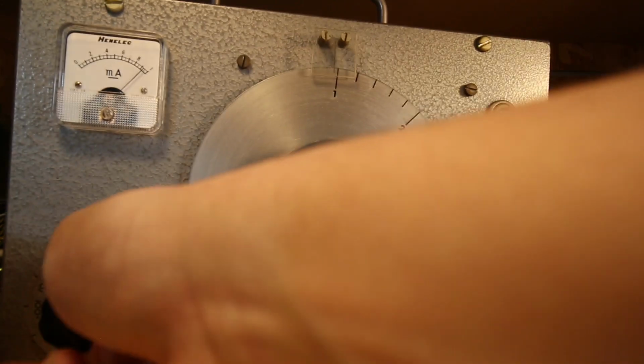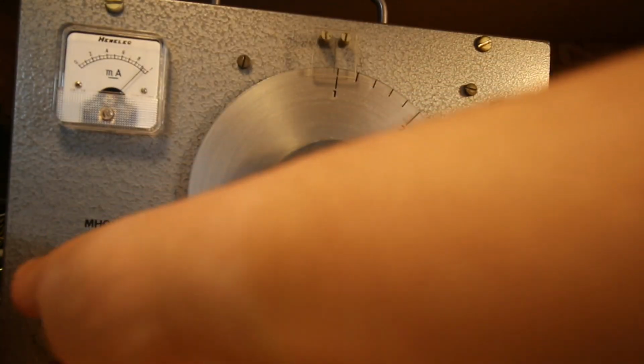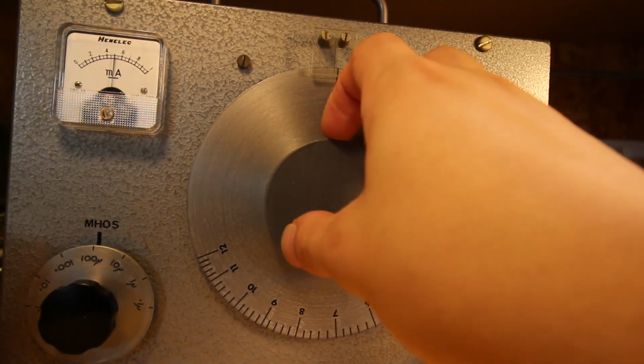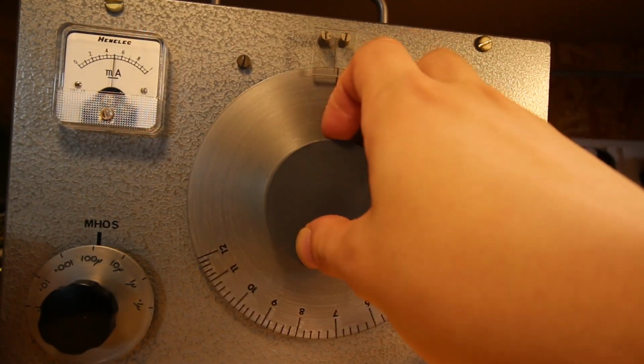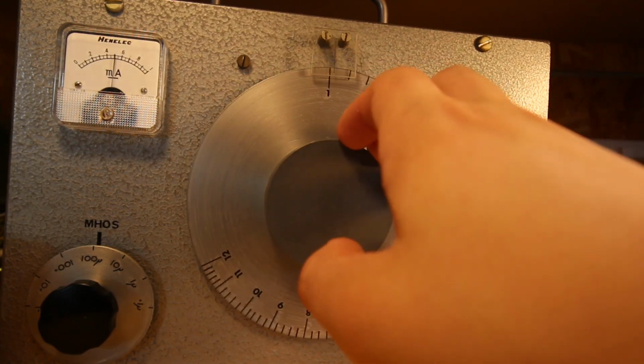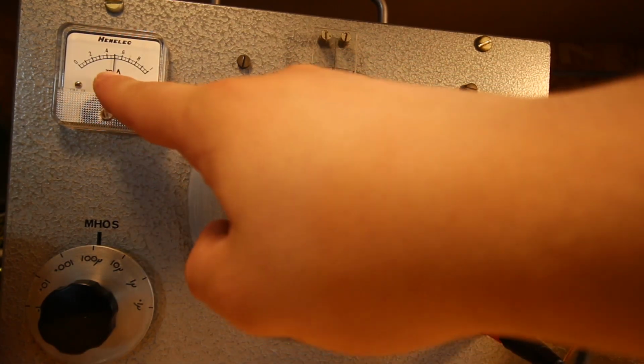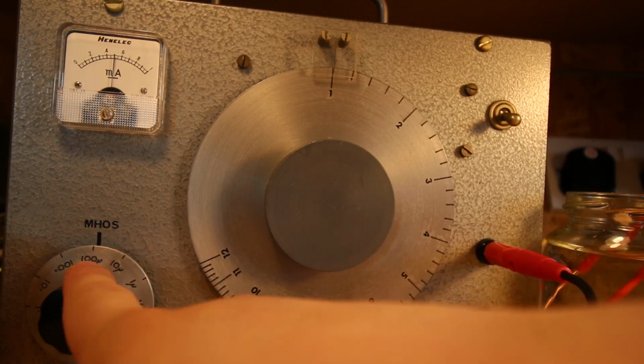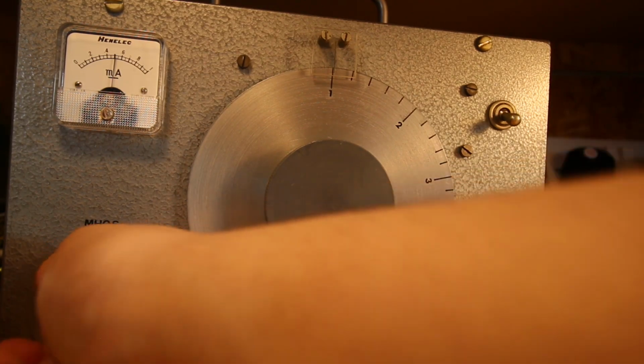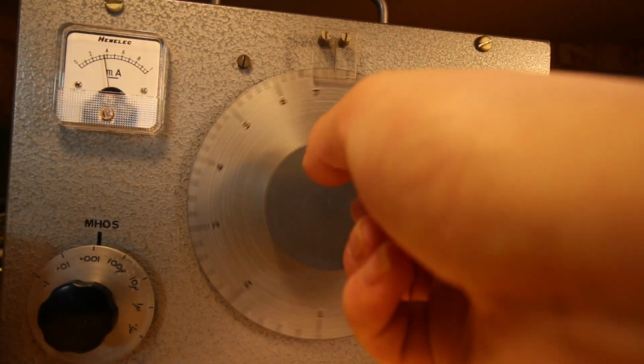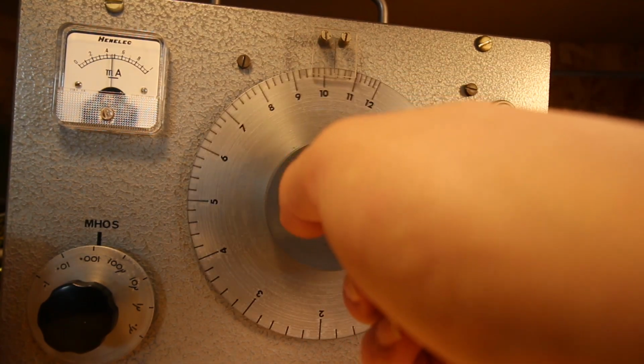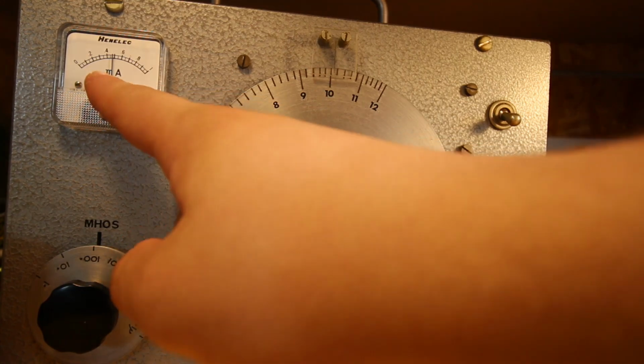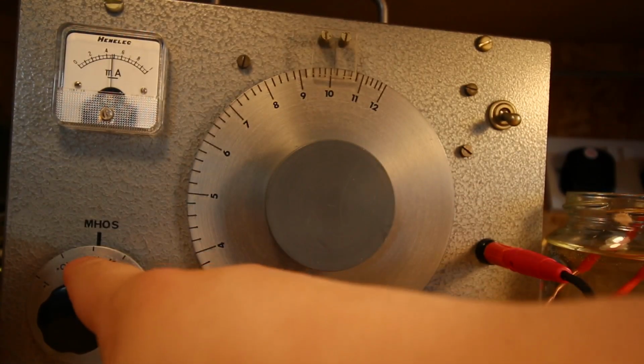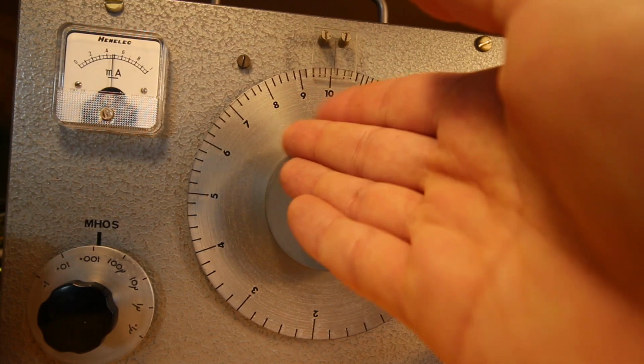I turn this, it does not go to about halfway, so this is wrong - still off, there we go. See, so that's gone to halfway there when I set that to 100 micro. As I turn this, it goes up, and as I turn it back, it comes down. So when I set it to 1, that's on half, so 100 microsiemens is my measurement. And then when I turn this down, again, you can retune it back to 10, and it goes back to half. So this is 10 times less, 10 times bigger reading, same reading.